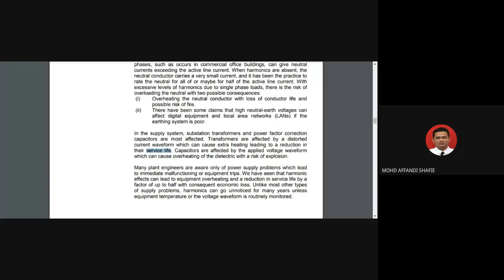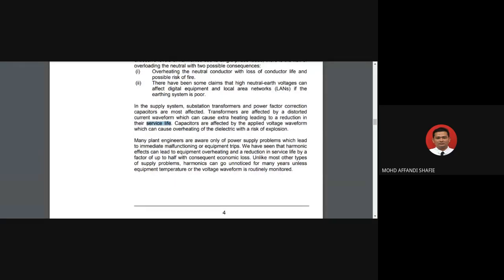So kita kat situ kita nampak dia punya keburukan lah, dia punya disadvantage of the harmonic distortion lah. So capacitors are affected by the applied voltage waveform which can cause overheating of the dielectric with a risk of explosion. So boleh meletup lah kapasitor kalau harmonic tinggi. So many plant engineers are aware only of system problems which lead to immediate malfunctioning or equipment failure. So we have seen the harmonic effect can lead to equipment overheating and reduction of the service life by a factor of up to half with consequent economic loss.